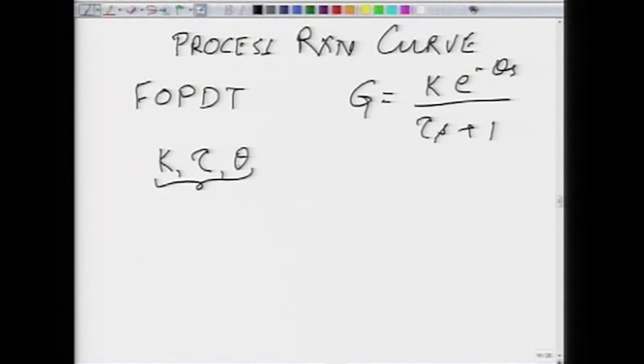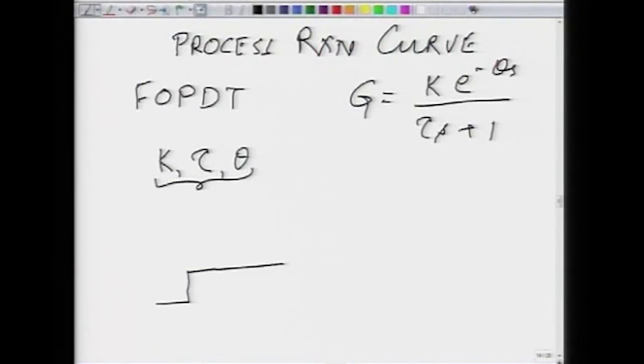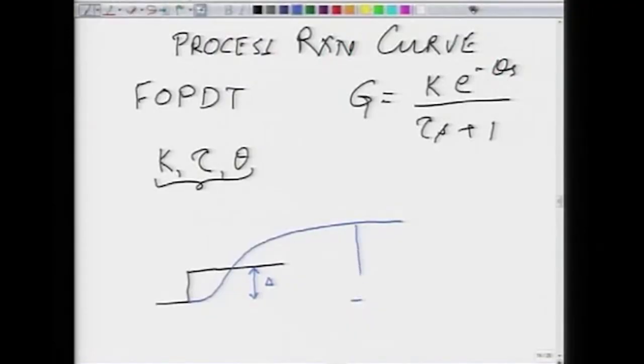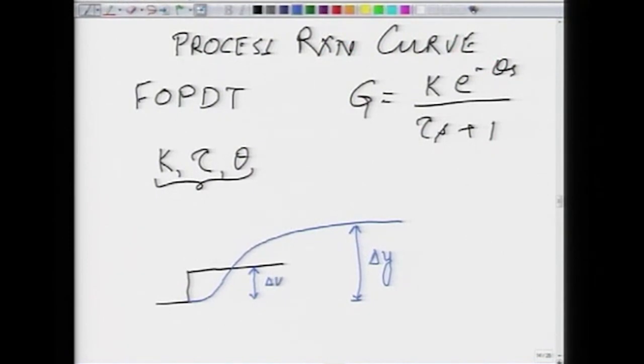These are parameters we want to estimate. One of the ways of doing it is the process reaction curve method. What we do is give a step change of a certain magnitude — for example, a 5 percent change in the position of a valve — and in response the process output responds like an S-shaped curve, settling to a final steady state value. If the change in output is delta y and the change in input is delta u, then the gain is delta y divided by delta u.